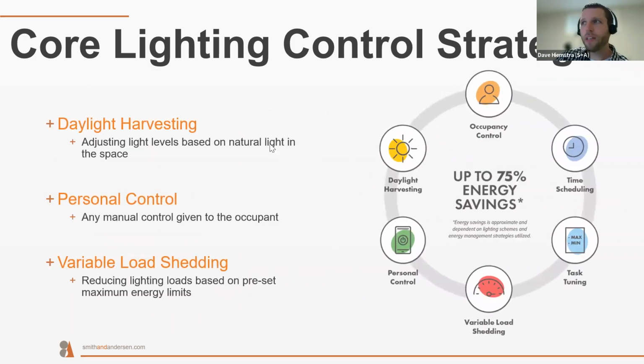Daylight harvesting is the idea that we're going to put a sensor into the space and measure the amount of natural daylight coming in, or the overall brightness of the space. Then we're going to adjust our artificial lighting based on that natural light. It's part of most energy codes right now, but it doesn't give us a lot of bang for the buck. I'd expect to see lighting controls in future energy codes start to step away from this, because it's rarely calibrated properly, rarely programmed properly, and more often than not it's the first thing that gets deactivated in the lighting control system.